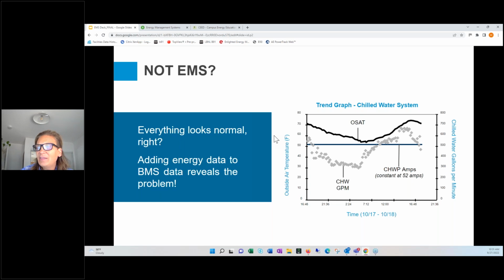By adding this piece of data, now we revealed a problem because ultimately it shouldn't be a straight line. As the GPM goes down, our pump speed should go down, and therefore the power or the energy use on the pump should also kind of follow a similar pattern as those two lines, which is not what we're seeing. So by bringing in this energy data, in my mind, we're seeing the whole picture. Before we were not seeing the whole picture. And that's another advantage of an energy management system, is we're able to see a lot of different pieces of information together in one location.